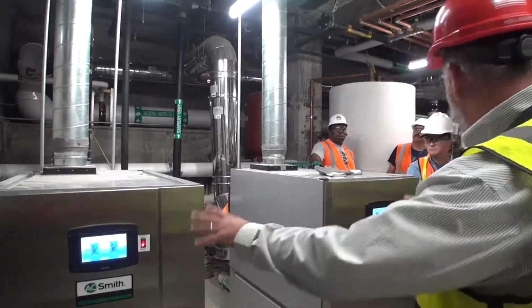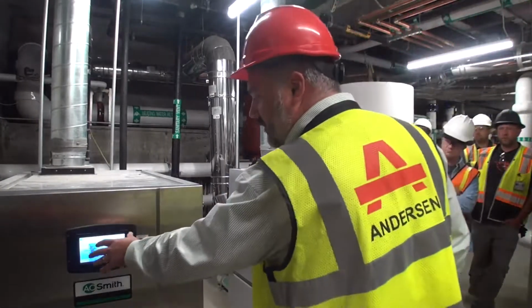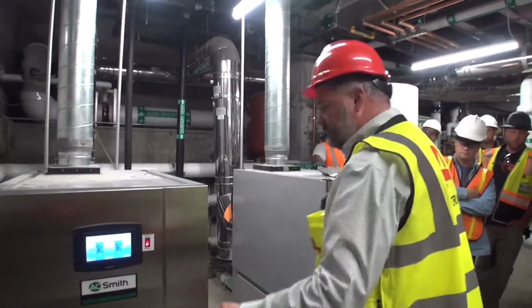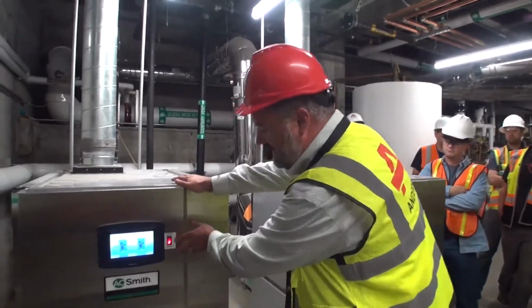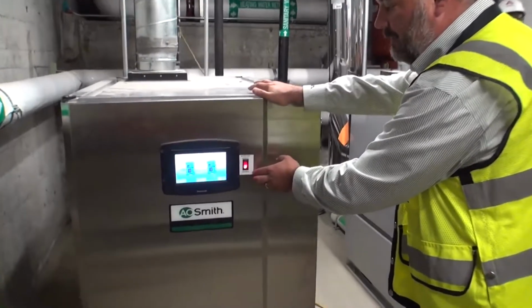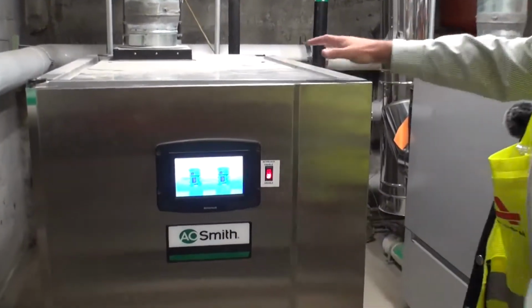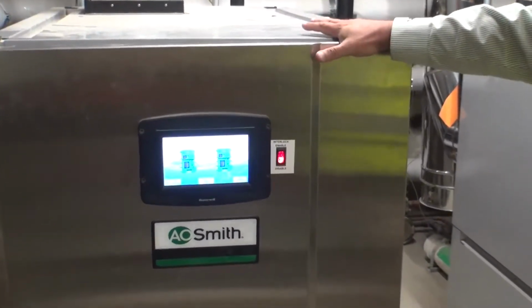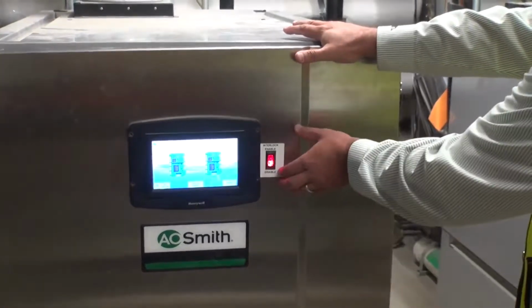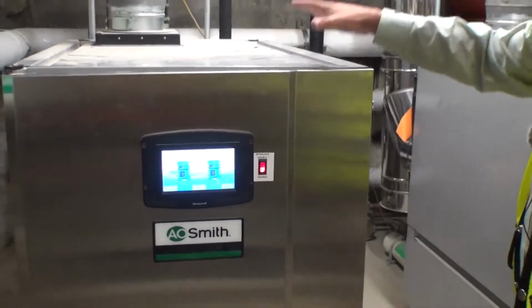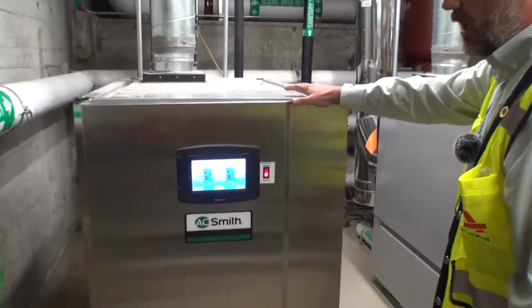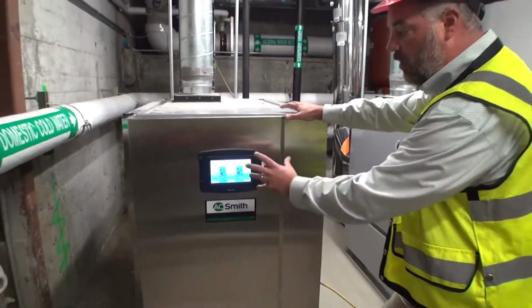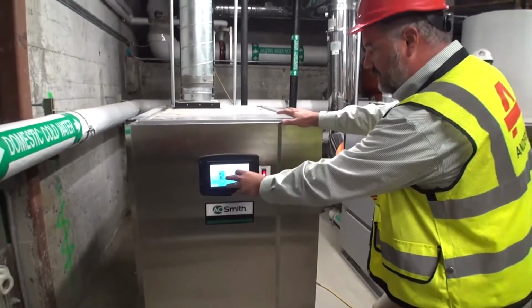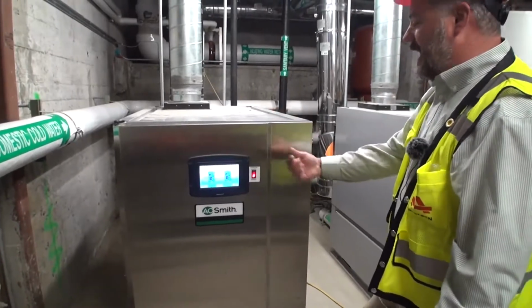A couple things when we look at these boilers. These screens here are all touchpad screens. When you look at it, you'll see an enable, disable button here. Enable, disable does not kill the power to these boilers. What enable, disable does is basically disable the function of the boiler, so it's not going to kick on, but you still have full power onto the boilers to actually look at the screens and make diagnostics.